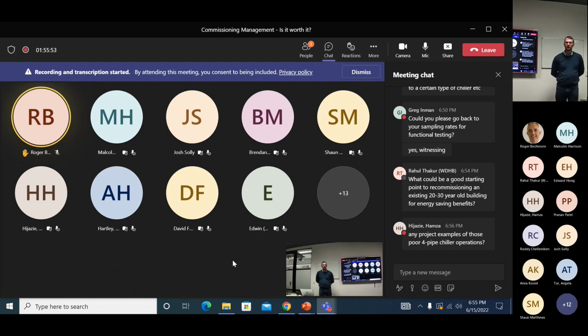Talk to somebody who understands commissioning to start with. They'll sit down - the BMS is a good start, it will generally tell you what's working and what's not. Even if the BMS isn't commissioned correctly and the information coming in is wrong, if you're experienced enough you should be able to pick that up fairly quickly. Looking at the trend logs in certain areas will soon tell you whether the controls are working - if the chiller comes on and the temperature goes up, clearly something's not right. So spend a few days with the building management system if you've got one.